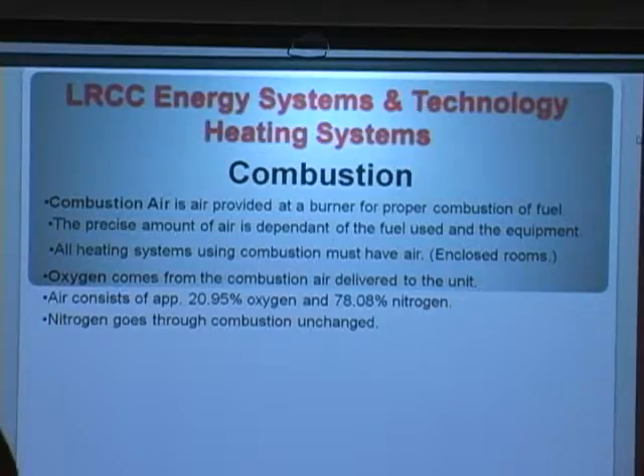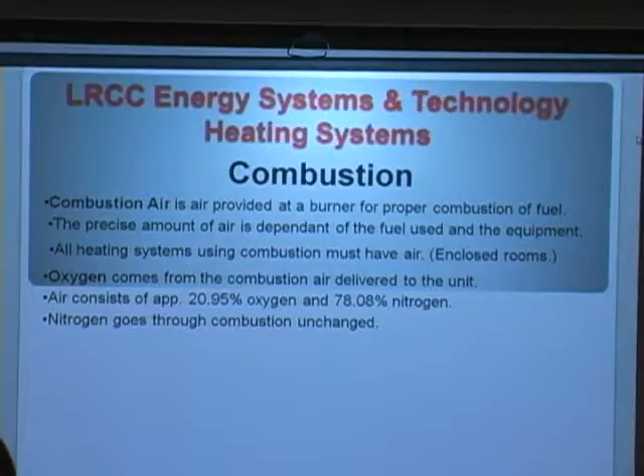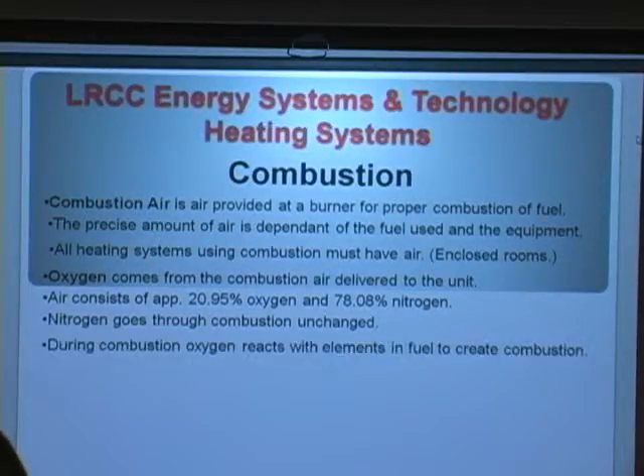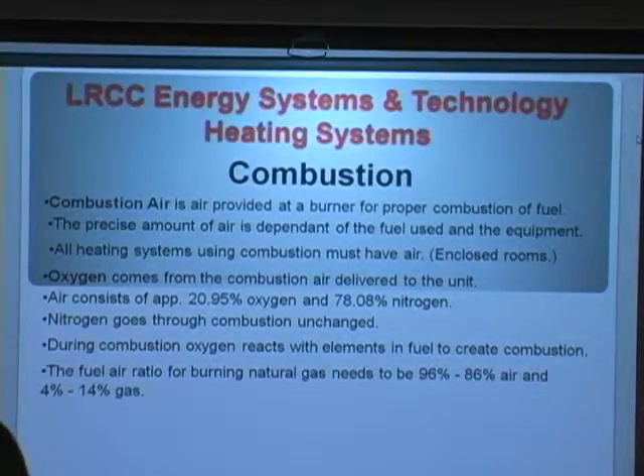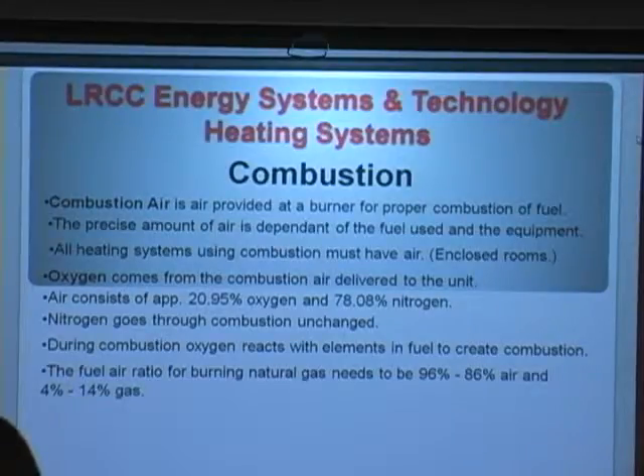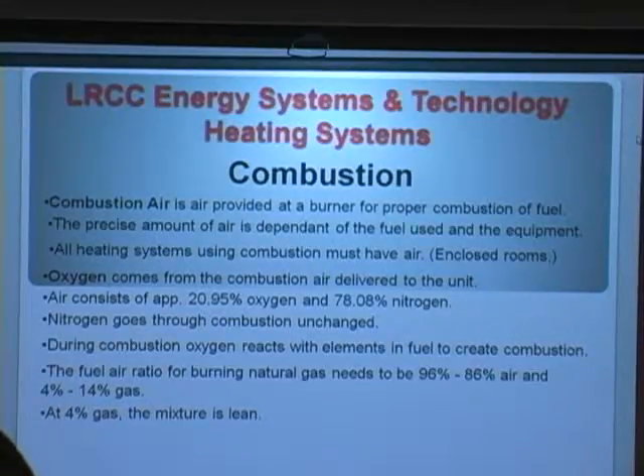Nitrogen just passes through the flame and does not change state at all. So if you have 10 grams of nitrogen going into the flame, you'll have 10 grams exiting in what we call combustion byproducts. During combustion, the oxygen reacts with the elements of the fuel. The fuel-air ratio for burning natural gas needs to be about 86% to 96% air and 4% to 14% gas — depending on whether you're using an atmospheric burner or a forced air burner. At 4% gas, we consider that a lean fire.